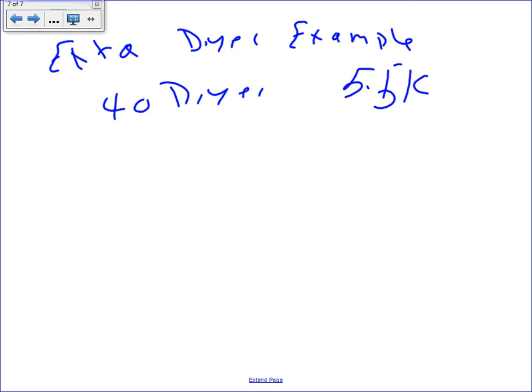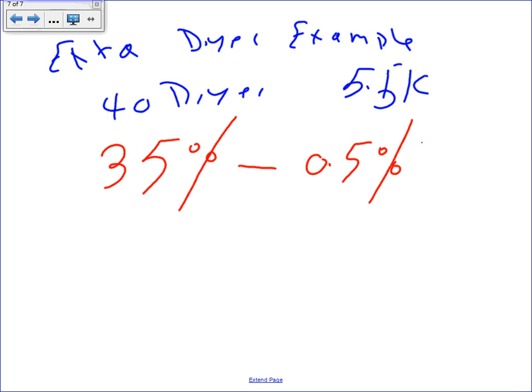So if you look at the 40, it will put me in the same location that I was in. I'm going to start writing the following. The demand factor: 35. I hate to write it, but I'm going to write the percentage here, minus 0.5 percent multiplied by the number of dryers. How many dryers do we have? 40, minus the magic number that they have for us, which is 23.